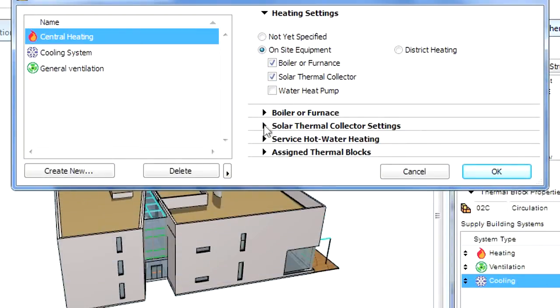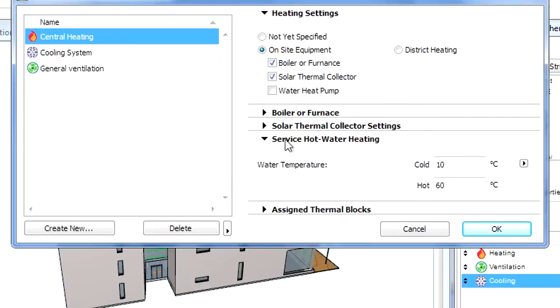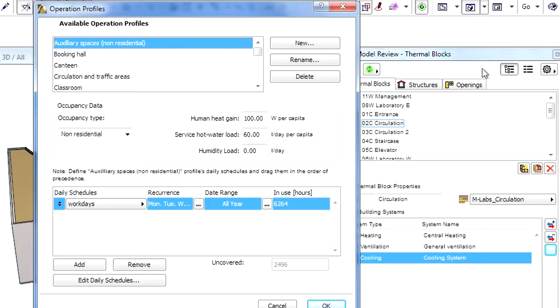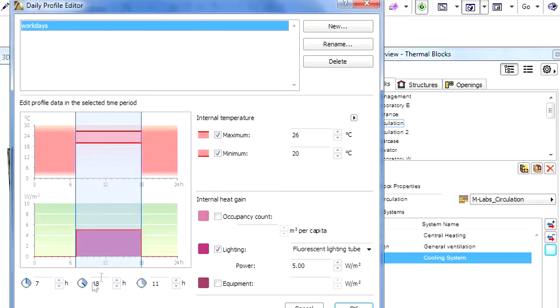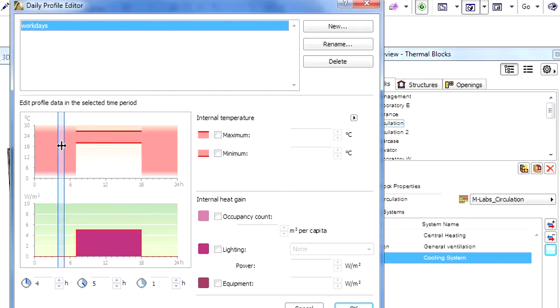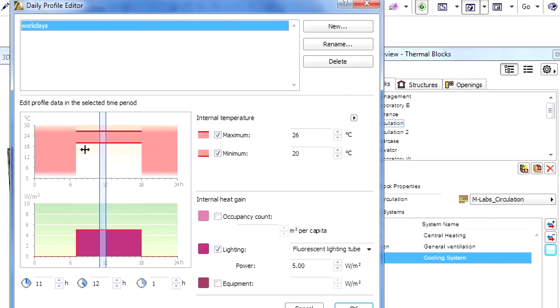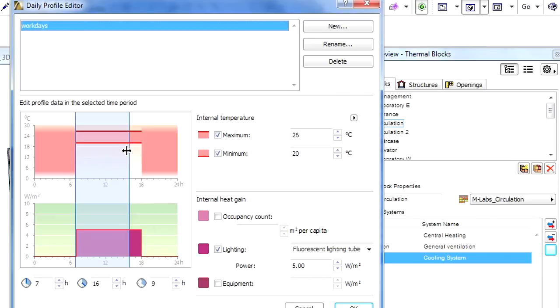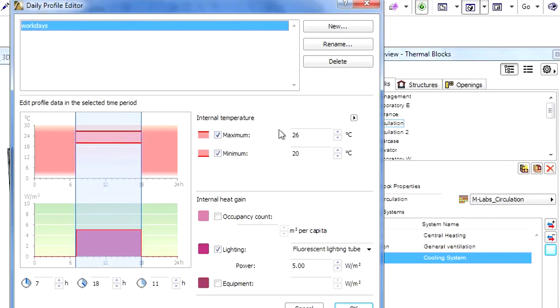Let's select Boiler or Furnace for the heating type and see how it works. Let's open the Operation Profiles dialog and display the Daily Profile Editor. Please note that the working hours on workdays have a minimum and a maximum threshold for the internal temperature, while the non-working period does not have such constraints. Energy Evaluation considers this information together with the shape of the building, insulation and external temperature to determine the energy demand of the building.